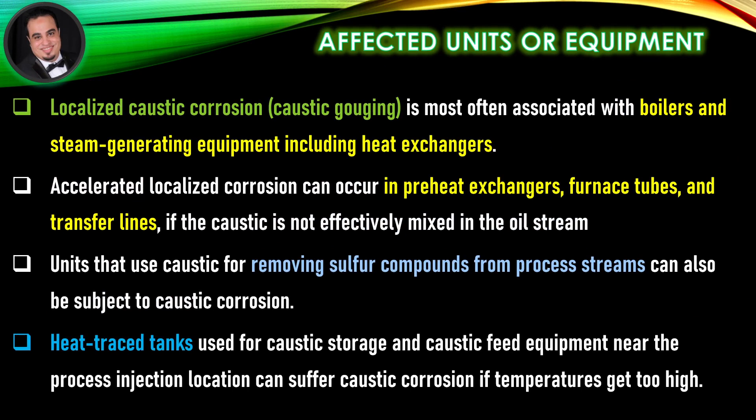Affected units or equipment: Localized caustic corrosion, or caustic gouging, is most often associated with boilers and steam generating equipment, including heat exchangers. Accelerated localized corrosion can occur in preheat exchangers, furnace tubes, and transfer lines if the caustic is not effectively mixed in the oil stream. Units that use caustic for removing sulfur compounds from process streams can also be subject to caustic corrosion. Heat-traced tanks used for caustic storage and caustic feed equipment near the process injection location can suffer caustic corrosion if temperatures get too high.